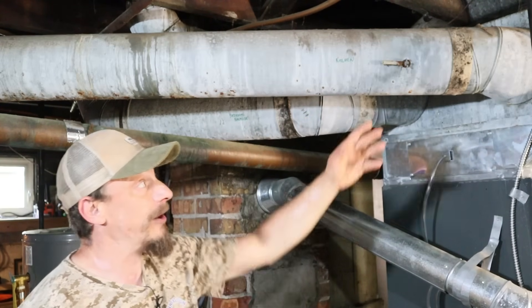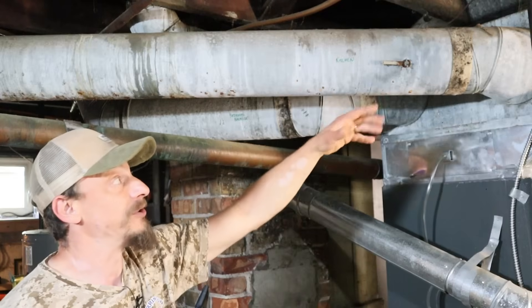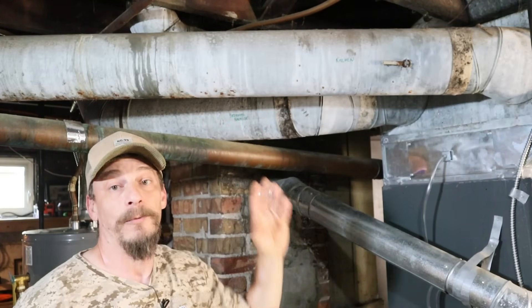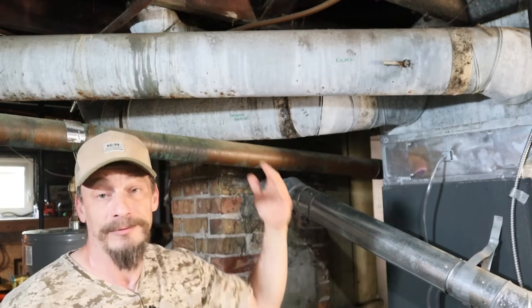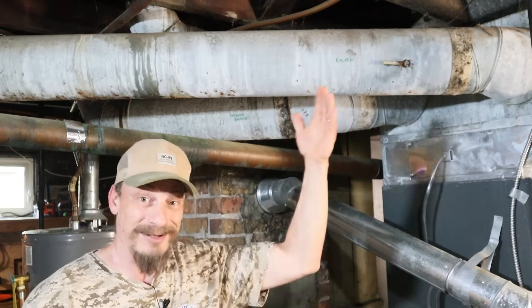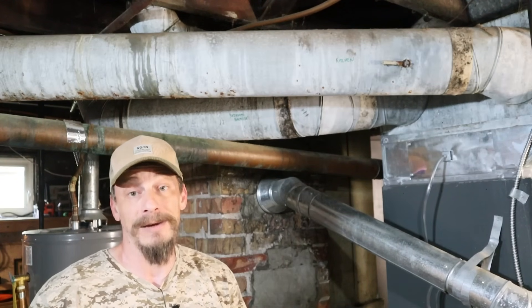This is exactly why I never just come in and bump up blower speeds to compensate for airflow issues on the first or second floor. I may just be making the problem even worse by increasing that pressure and increasing the tendency of the air to follow the path of least resistance - pushing even more air downstairs and less air upstairs.